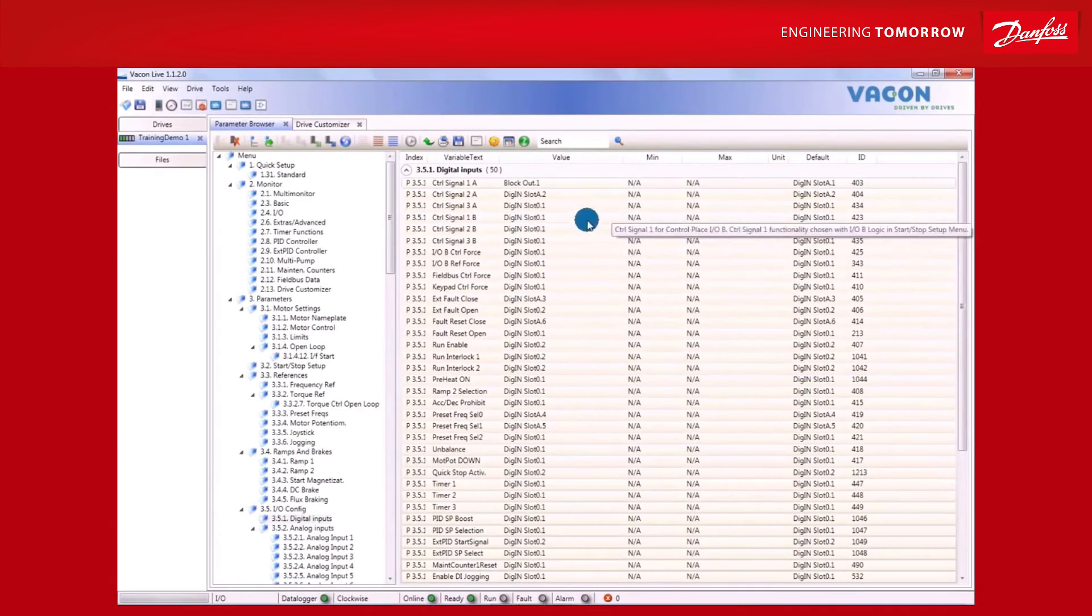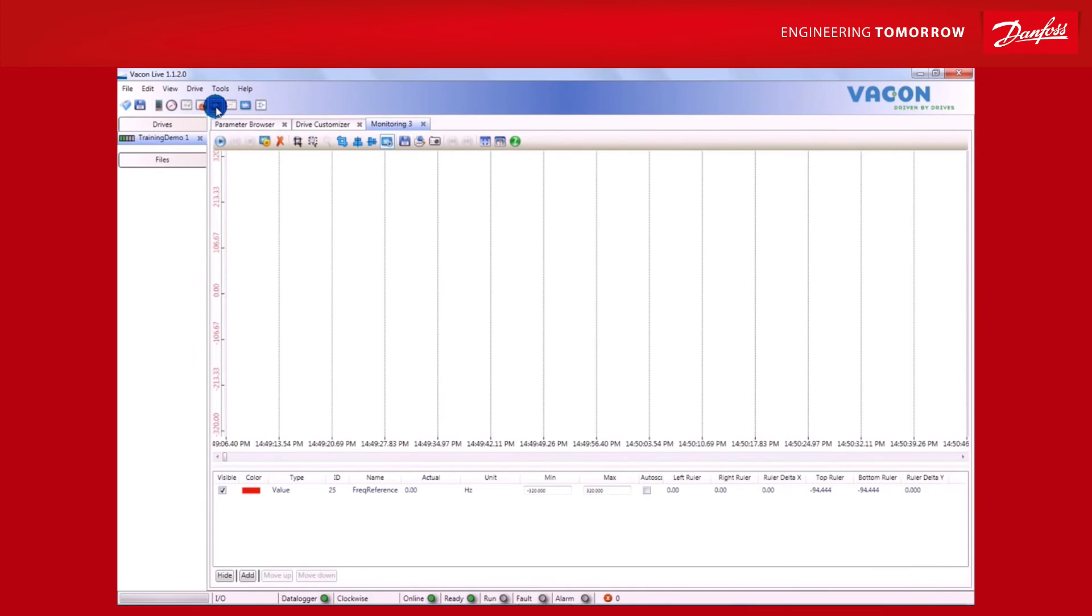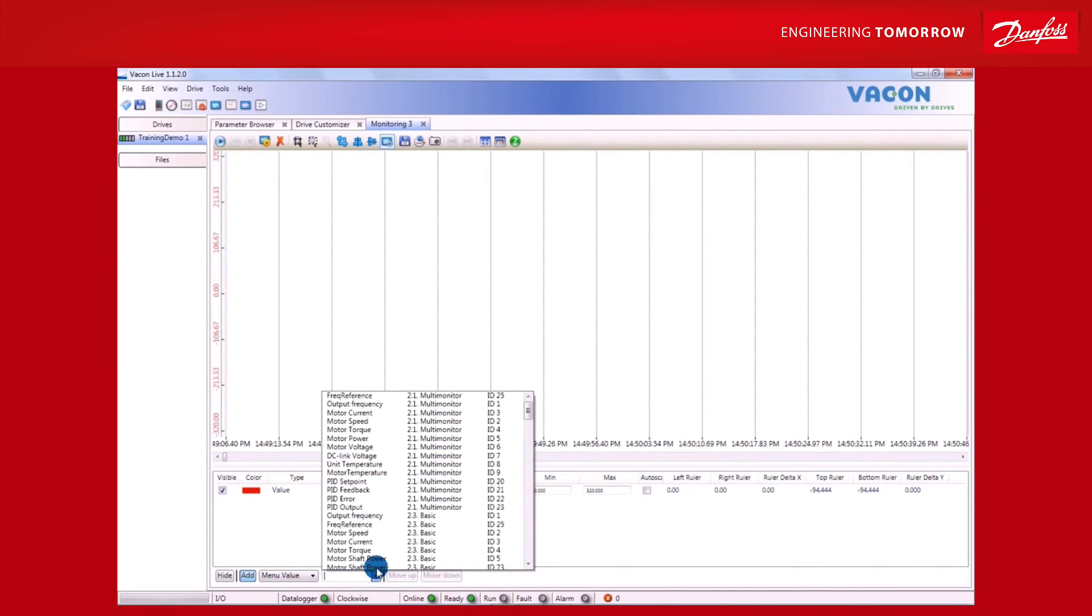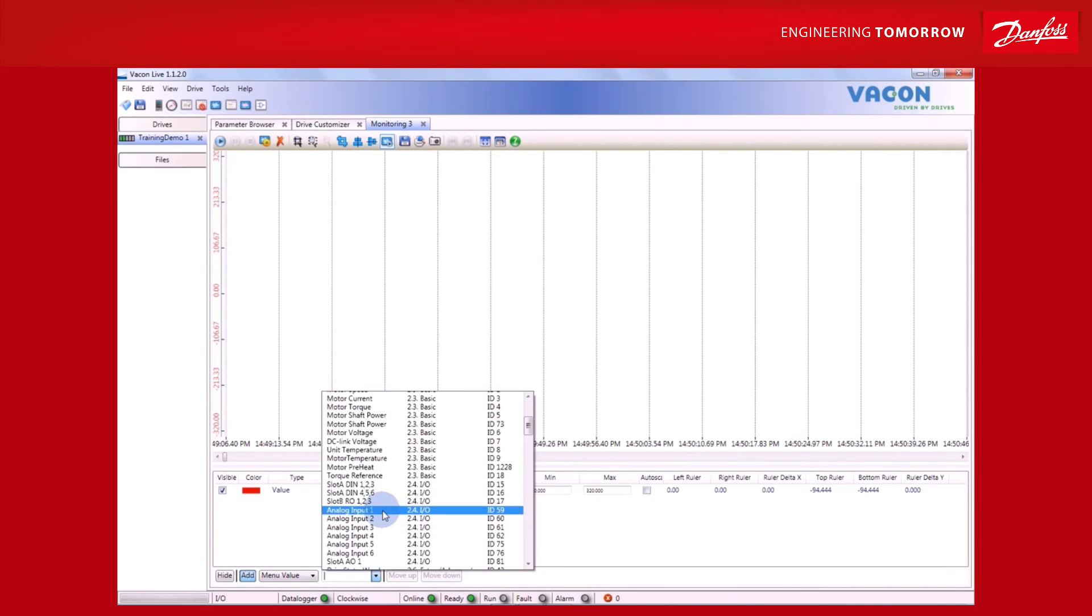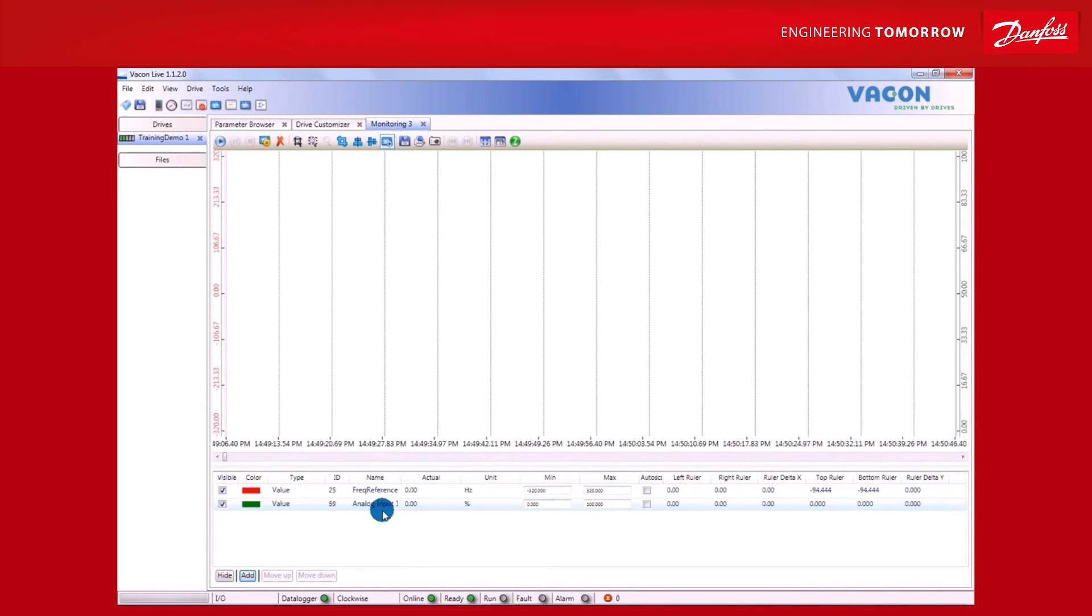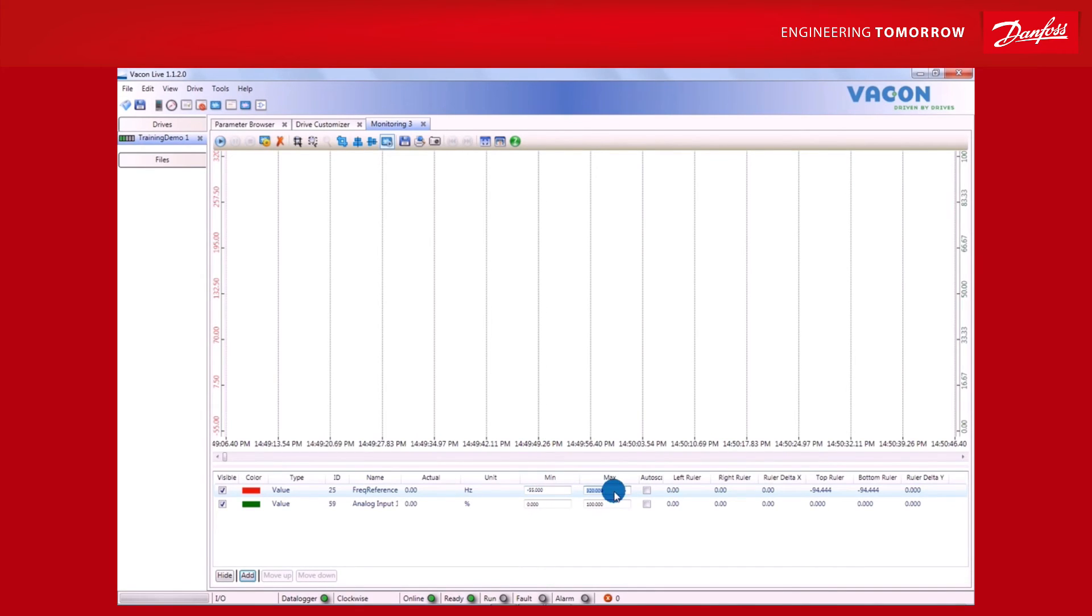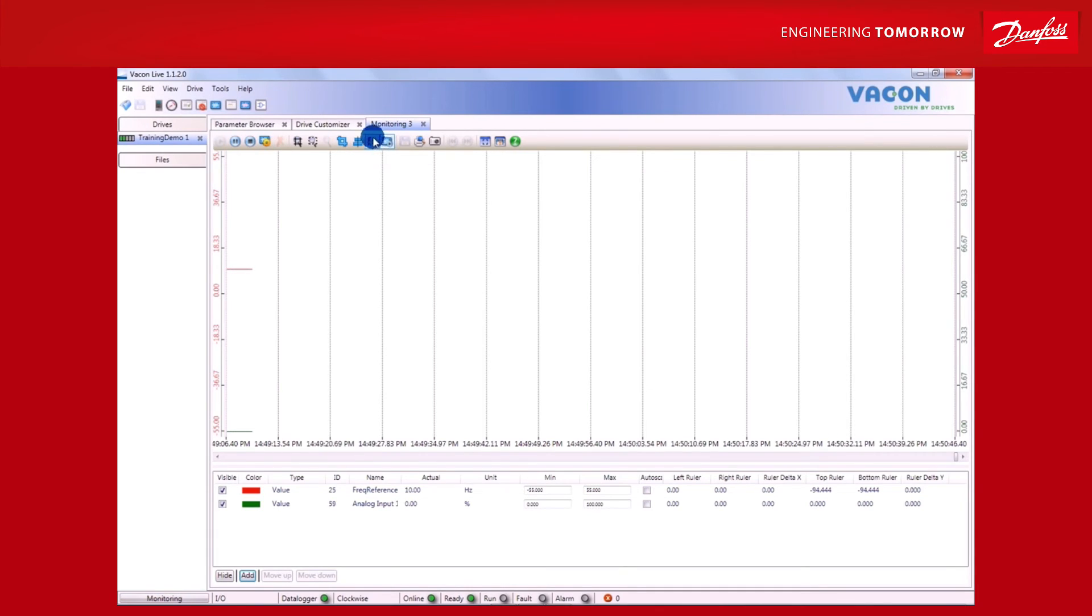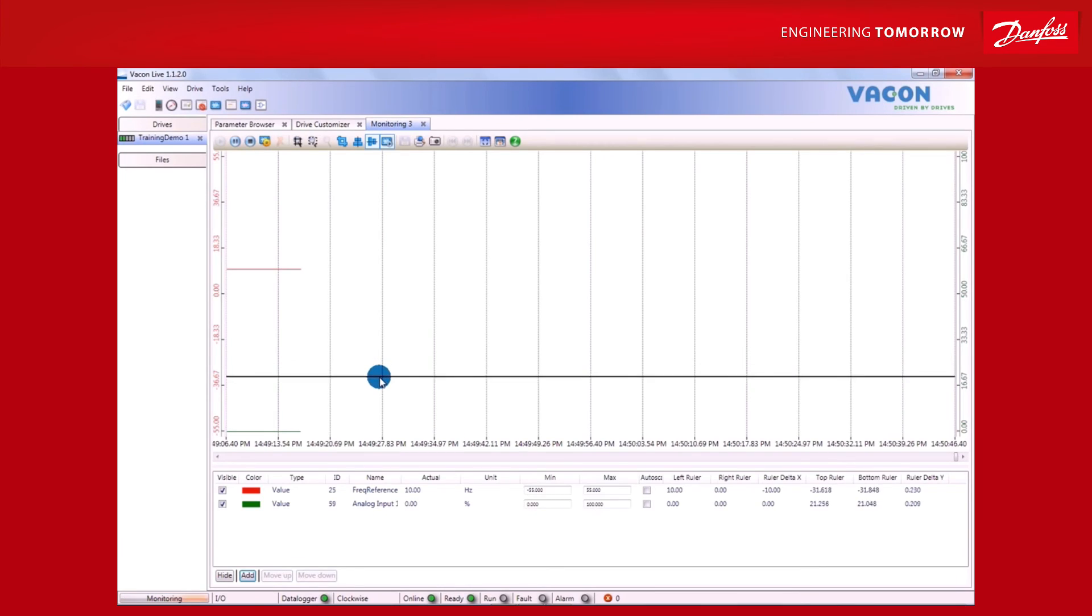Now to demonstrate this, we can also check it from the analog monitoring signals. When the special type editor window appears, select output frequency for monitoring, and then select the analog input. Now monitor 1 is selected, and a monitor window will appear, in which we can view the trends occurring within the selected set of monitoring values. The green line indicates the value of the analog input, while the red line shows output frequency trends.